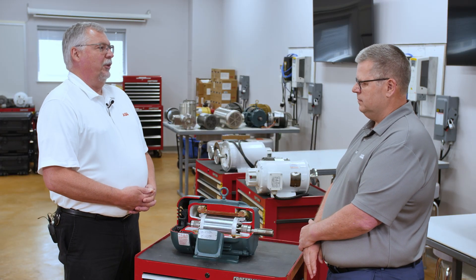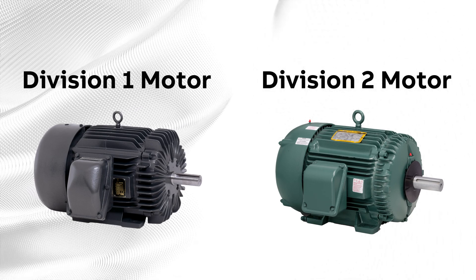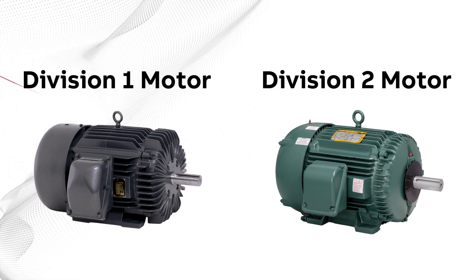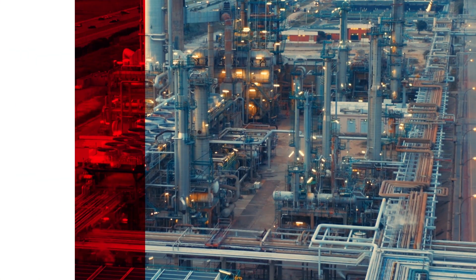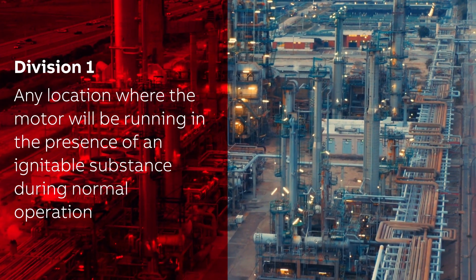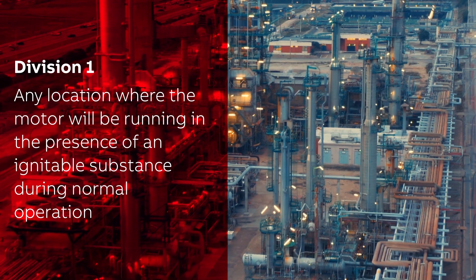Today we will be covering the differences between Division 1 and Division 2 when talking about hazardous location motors. The definition of a Division 1 area is any area where a motor will be running in the presence of an ignitable substance during normal operation. The ignitable substance can be present all the time or some of the time. The key point is the Division 1 motor will be operating in the hazardous substance during normal operation.